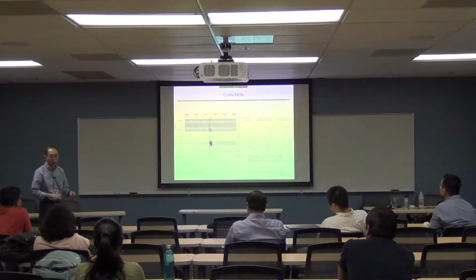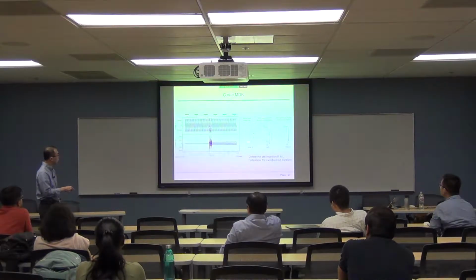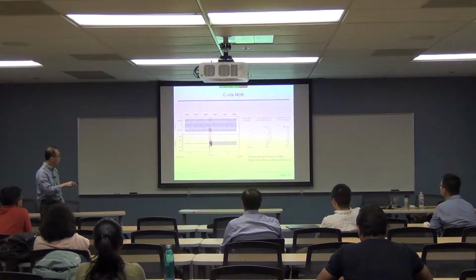You can see that in here initially this is the voltage measurement at 161 kV line to line, and no capacitor bank is available in service right now. So the condition is like this. Now when it is energized like this, this is the manifestation in voltage and current, and then immediately gone to here. So immediately in here, do you see any transient in here?